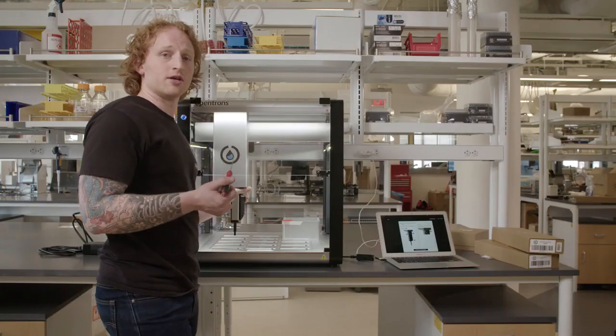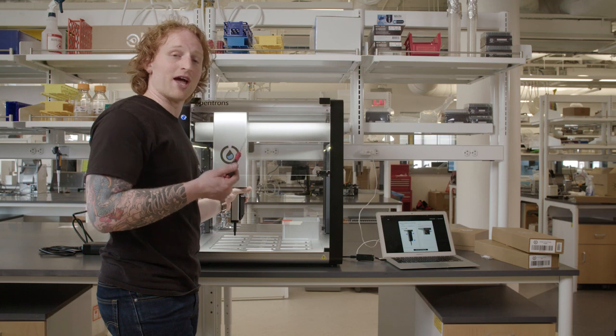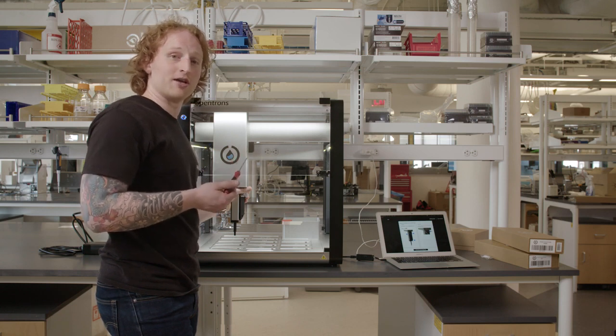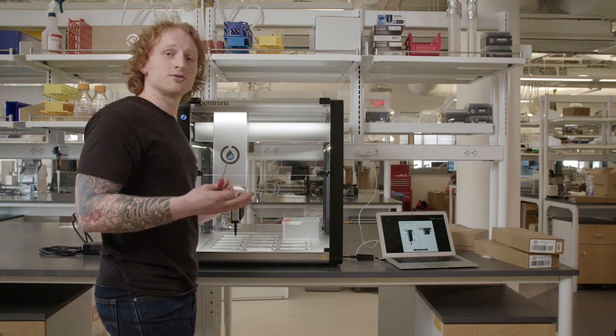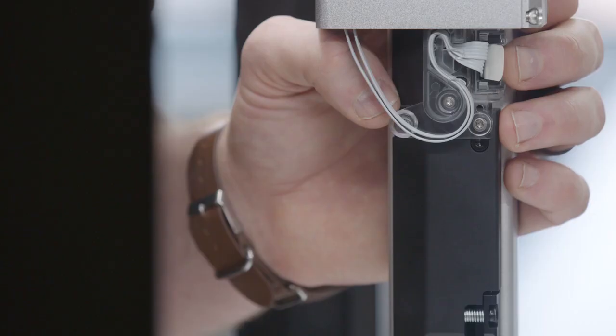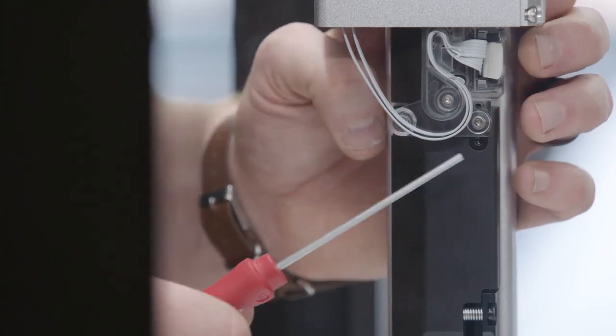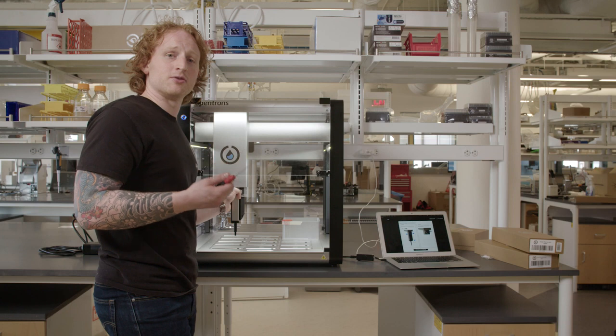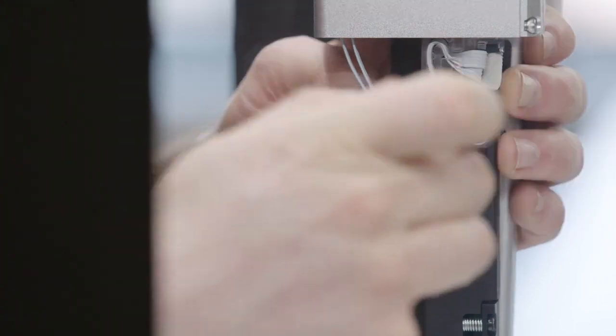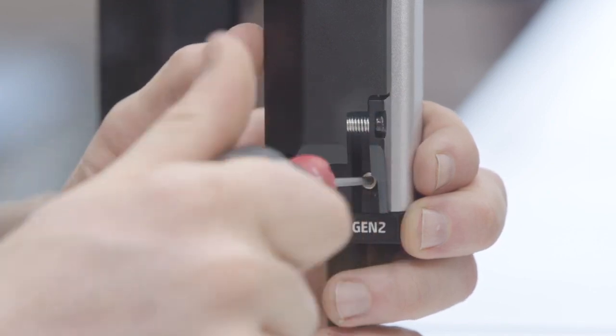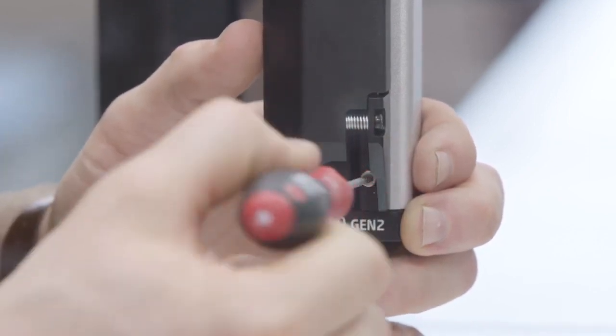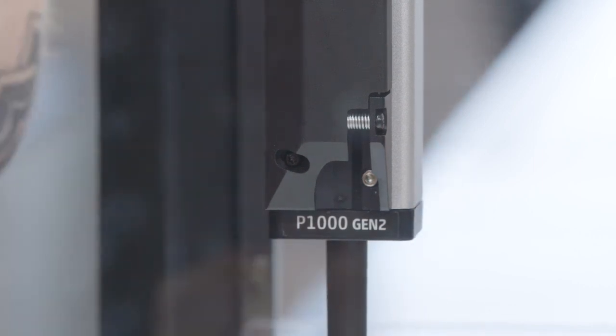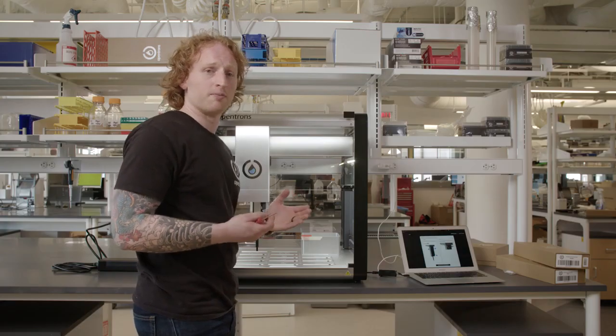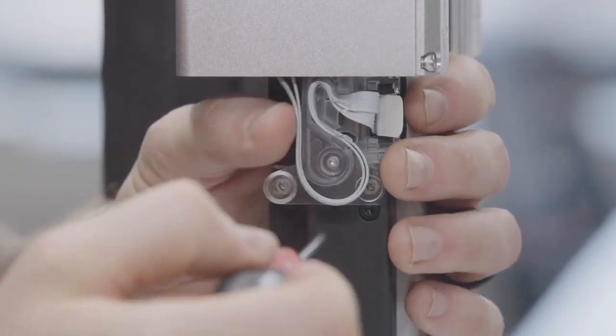There are a total of 3 2.5 millimeter hex screws that will secure the pipette to its mount. There are 2 top screws which are permanently embedded in the transparent plastic at the top of the mount, and then 1 screw which I need to insert myself. I will screw in the top 2 screws first, making sure not to tighten them all the way. Then I will screw in the bottom screw, making sure that the pipette is straight up and down. I have a single channel pipette this time, so I will screw in the bottom screw all the way. Last, I will tighten the top screws all the way.